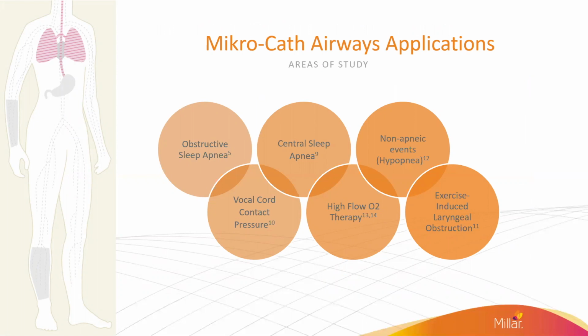In addition to sleep apnea studies, the Mikro-Cath has shown promising results for collecting high-fidelity data during non-apneic events. Since the sensor measures pressure changes by deformation strain, the Mikro-Cath can be placed in pleural spaces to measure pressures during high-flow oxygen therapies. Finally, because it is a solid-state sensor unaffected by motion or resonance, the Mikro-Cath has been validated for studying laryngeal pressures during exercise and vocal cord contact pressures.